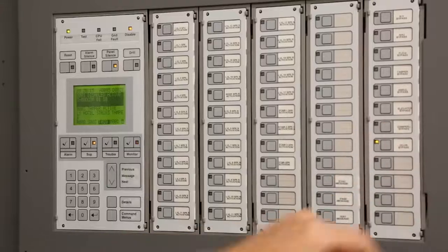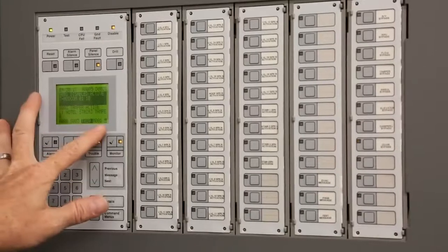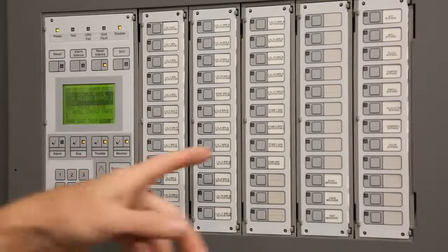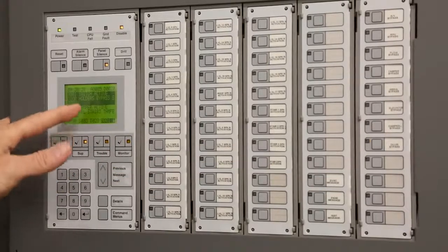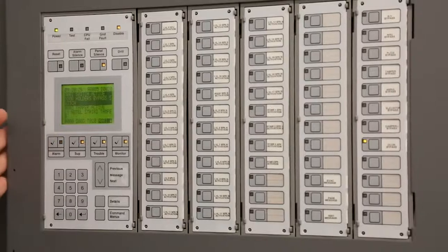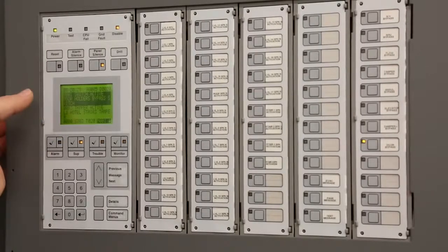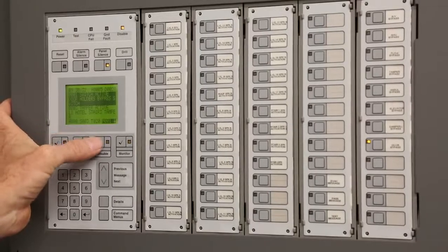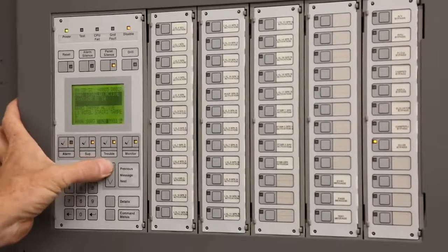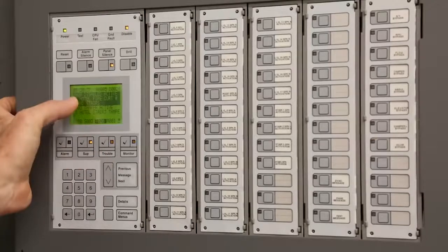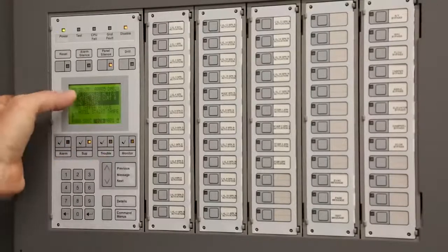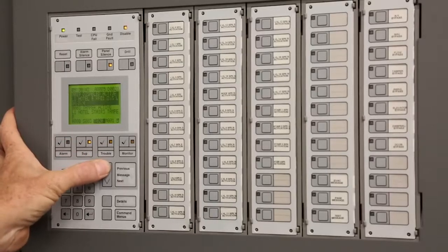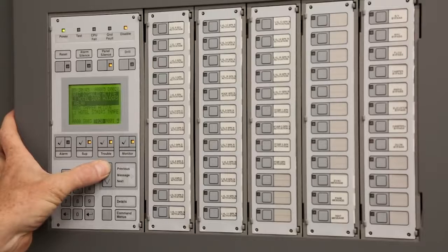For instance, like I said, right now we hit door bypass. If you notice, we got a monitor point active. If you want to know what it is, just hit monitor points, and it'll be more descriptive. It'll say right here that the switch is active, door holder switch. So basically it's saying that the doors are bypassed. If you notice, the troubles went from 1 to 20 now, and we can scroll through them, go up or down arrow. Highest right there is 20, and they're all disable active. So right now, if we were doing any testing, these doors would not activate.